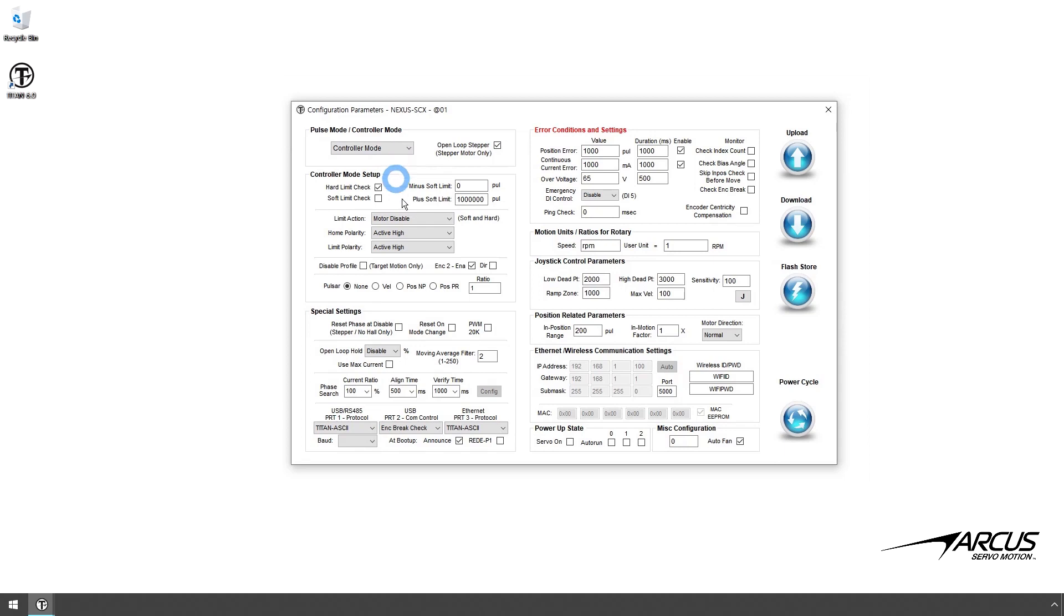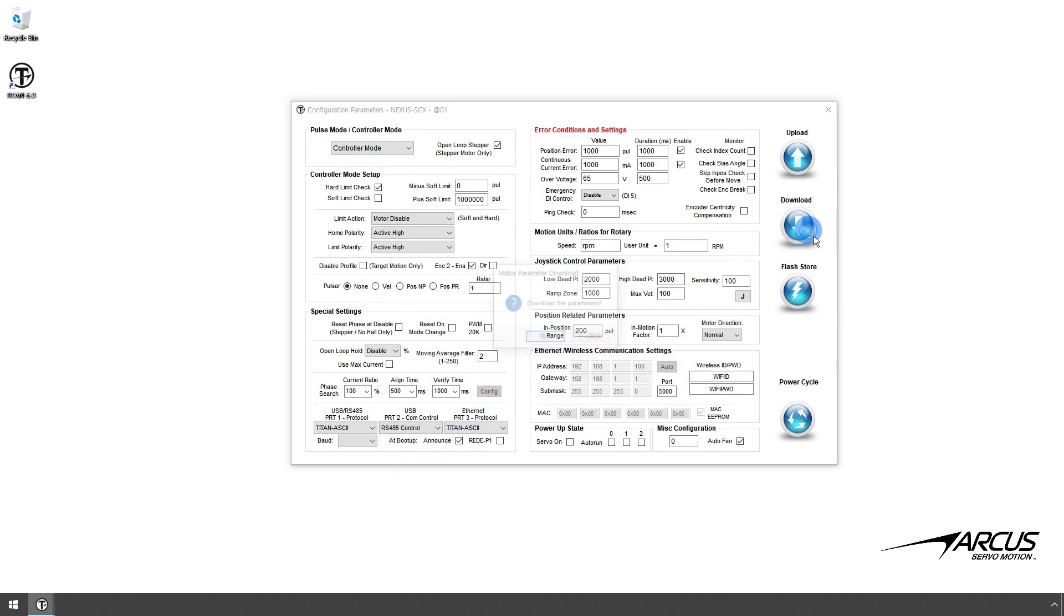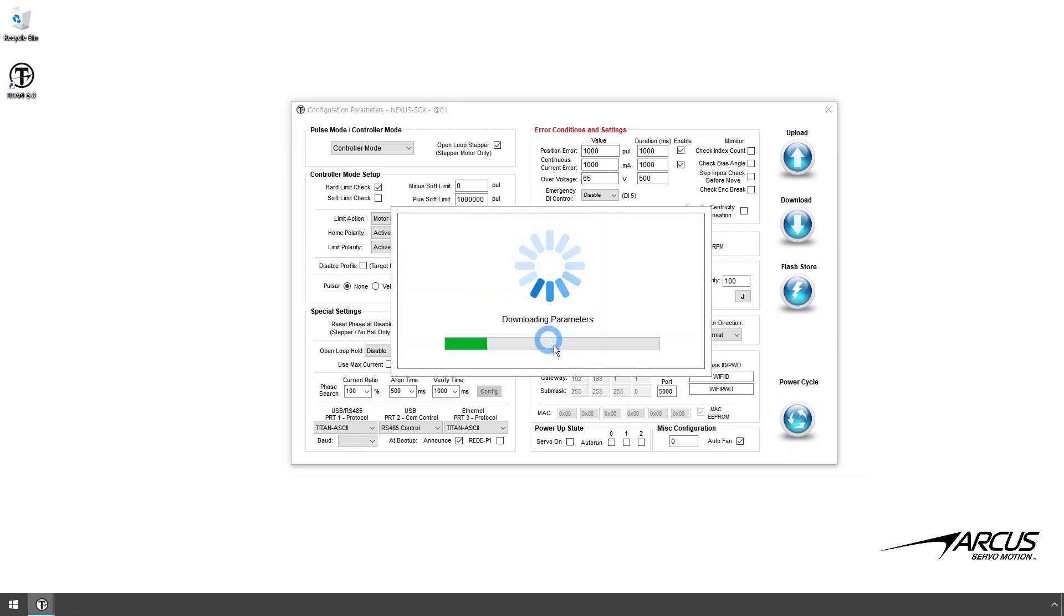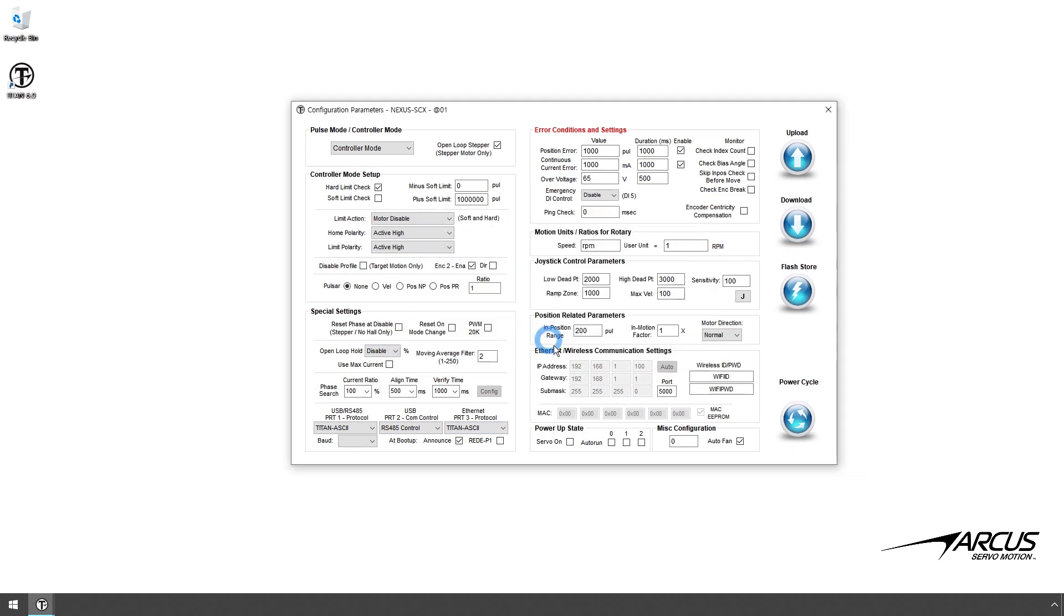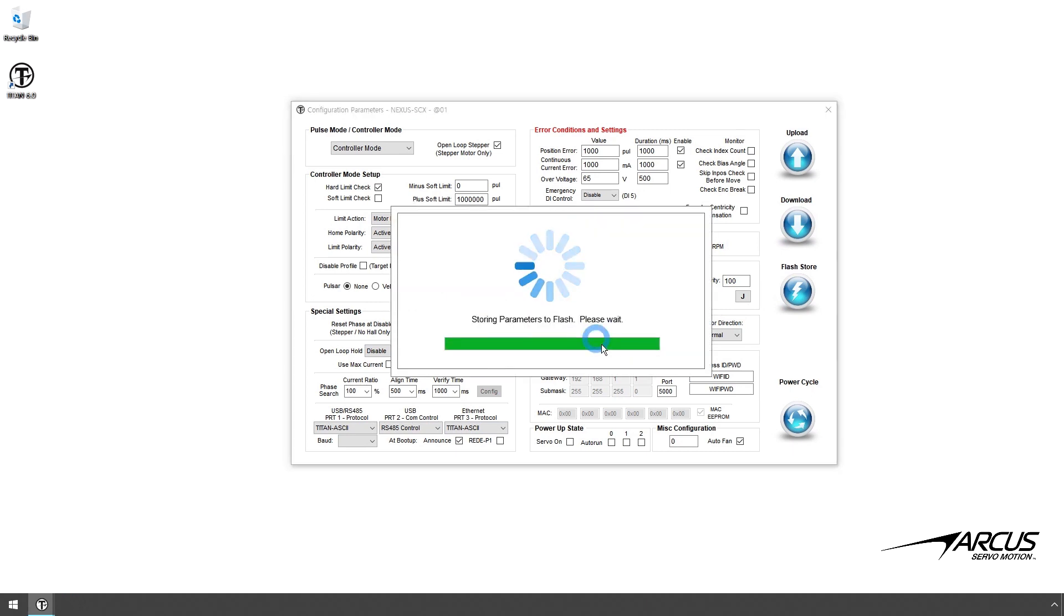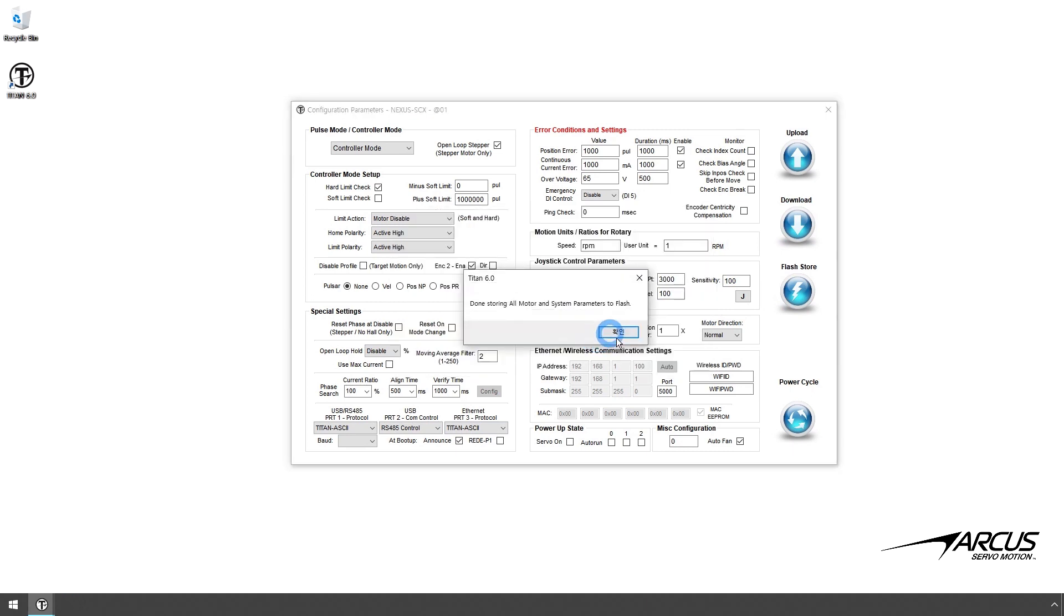If the encoder is not used, disable the encoder brake check. Download the parameters. Let's store the parameters to flash, so that in case there is a power cycle, the settings are saved to the flash memory.